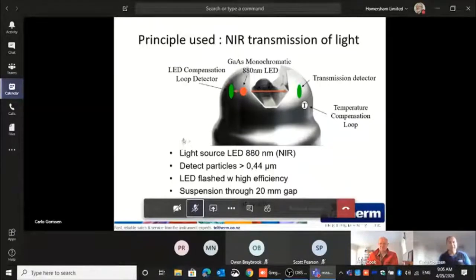So basically, the unit uses an LED with an 880 nanometer wavelength. That basically means that we can see particles that are bigger than 0.4 microns. That is the same as the filter you use in your dry weight sample. That filter is basically a 0.4 micron filter. So we can basically tell people that the accuracy that we have is the same as your lab sample. That's how you do a calibration, single point with the lab sample.